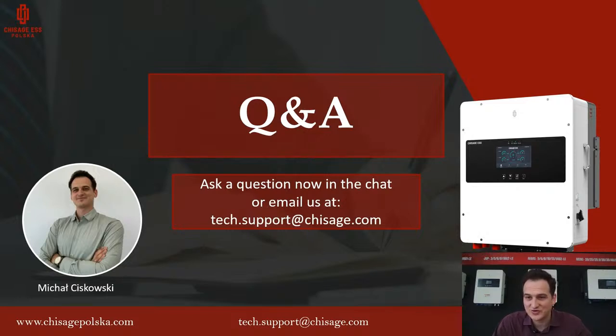How do the BMS and batteries behave in winter, at which temperature will the battery stop working? It stops working at minus 20 degrees Celsius. It will charge at more than 0 degrees. Below 0 it is not charging, but it discharges down to minus 20. Of course, the charging current will decrease, and the discharging current also decreases when the temperature goes low. And the other way, if the temperature goes higher, the charging and discharging current will go lower.